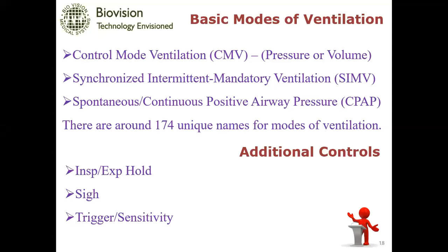There are a few other things like inspiratory and expiratory hold, usually used to take X-ray and all. You hold the breath in inspiration or expiration condition, that can be there in the machine. Sigh refers to a long breath. And trigger sensitivity I had already explained for the supportive mode of ventilation, right?